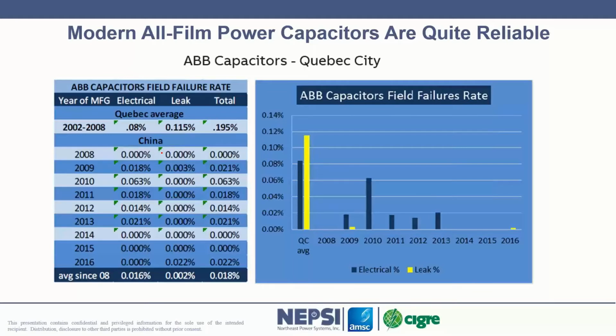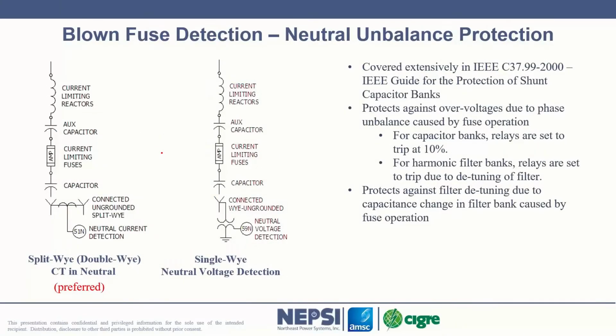But the key here is still to remember that increasing the voltage rating of the capacitor inside the harmonic filter will help to create a more reliable harmonic filter, because you're going to be stressing it less, and you're going to be paying pennies on a dollar to increase that.